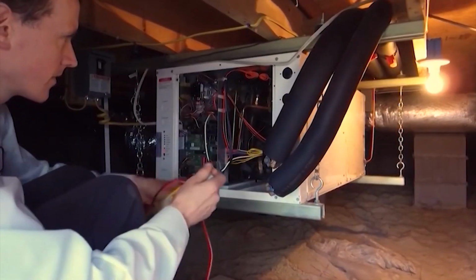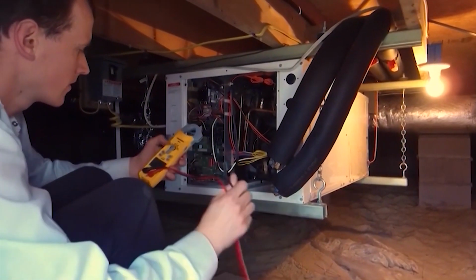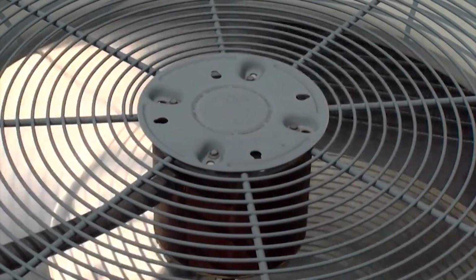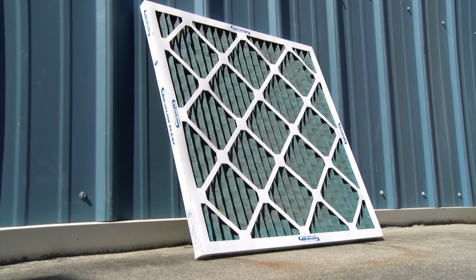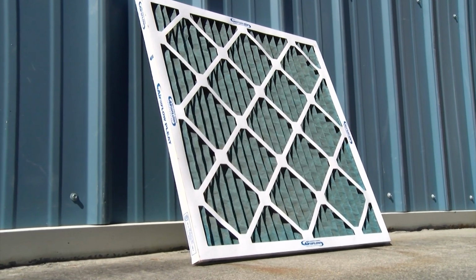They're running through a checklist of everything that's crucial for a functional unit this spring and summer. Obviously, we change your filters. We clean the drains, we put drain tabs in there, we check the condensate pumps. We also check all your start components, your electrical, contactors, capacitors, circuit boards, make sure everything's in tip-top shape. We check delta T's across the coil to make sure that the refrigerant pressure is good.